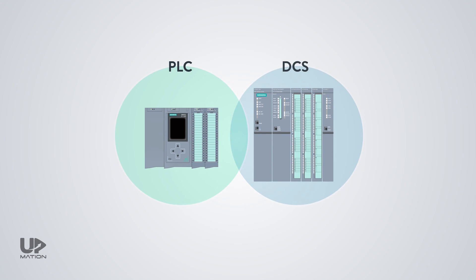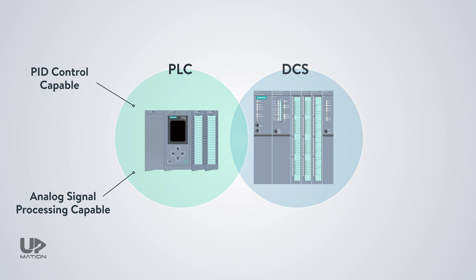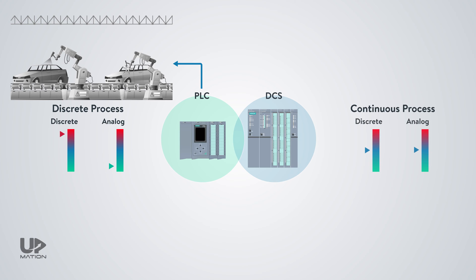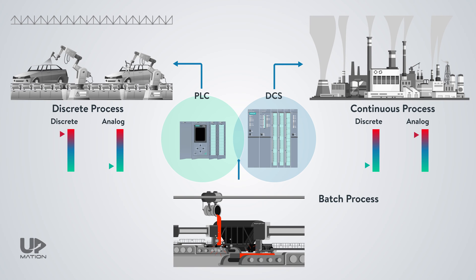Although PLCs have become more advanced and sophisticated, and are even able to control PID loops and analog signals, they are more appropriate for discrete process automation, such as the automobile assembly line, where there are lots of digital signals and few analog signals. DCS is more applicable for continuous processes with lots of analog signals and complicated PID control loops, such as processes in a power plant or a refinery. In batch or hybrid processes, like some steel-producing industries, DCS and PLC are used together, and there are overlaps in their functions.